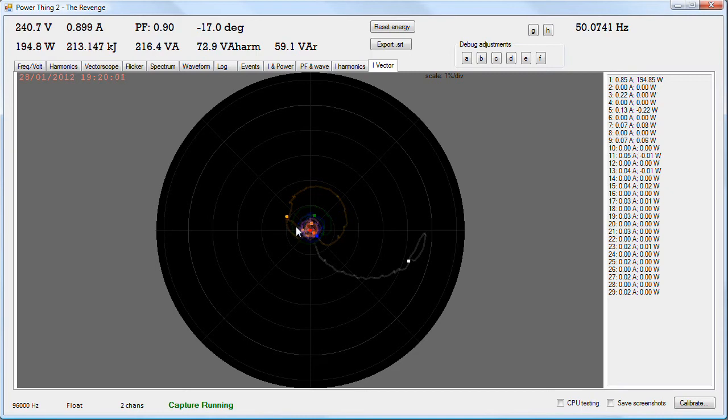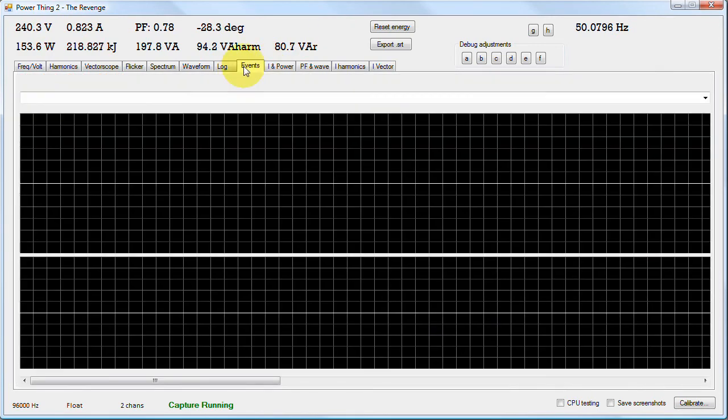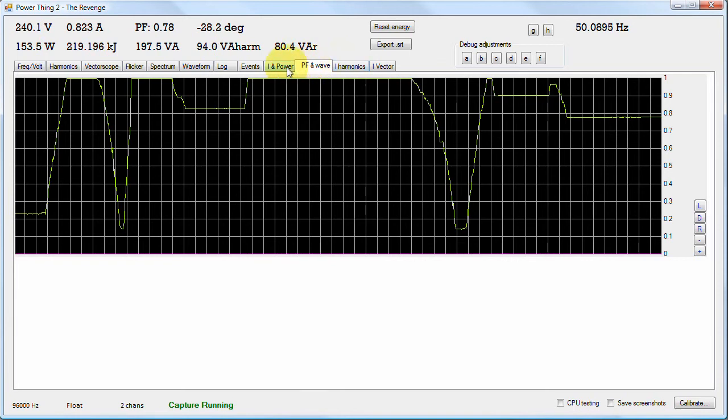As we distort the waveform due to the switching, the harmonic content, the 150 and the 250 and the 350 hertz components increase. And harmonics by and large don't carry useful energy. They simply take up current. They overheat transformers, they overheat power lines. They're a real nuisance. Transformers in particular are particularly susceptible to these. Harmonics have a lot more heating capability in transformers than normal power. So I hope you found that interesting.